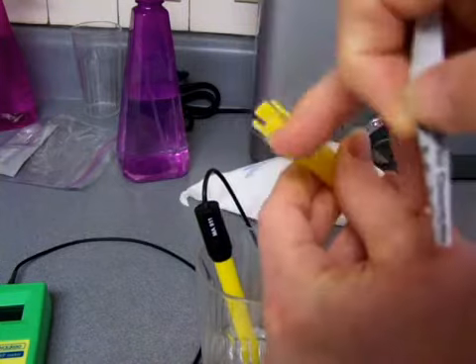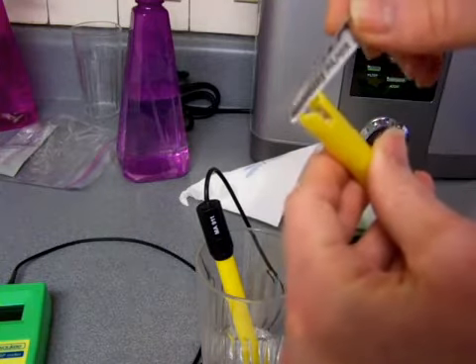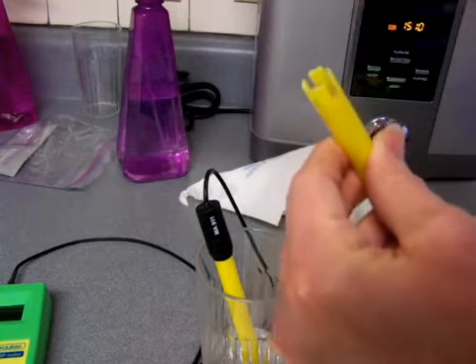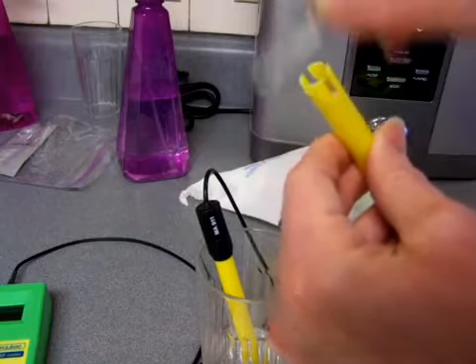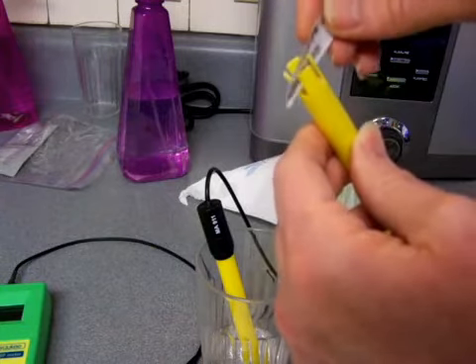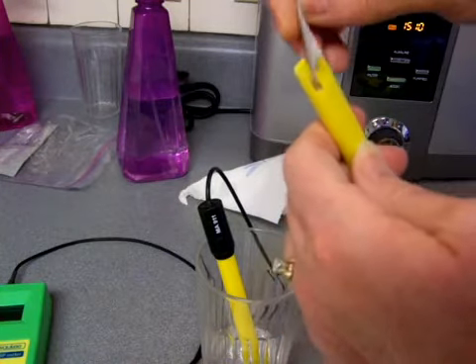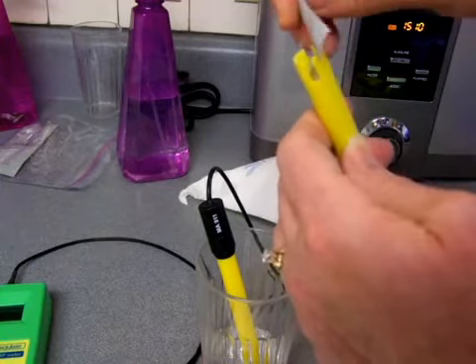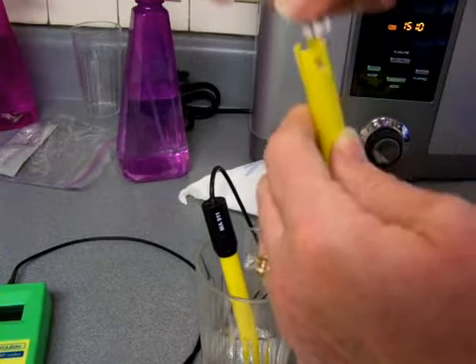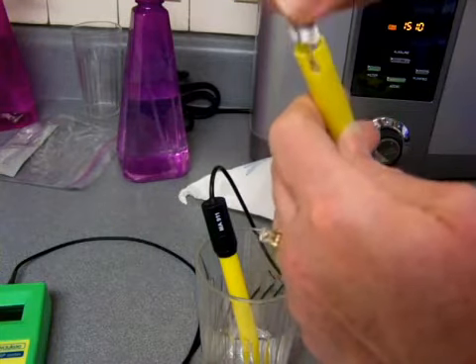And then I just go, there's little grooves here on the sides of the probe, and I just kind of go in the grooves and just do very light swishing and sanding. Very, very light, not hard. I don't want to do so roughly hard that I remove the platinum, of course. I just want to lightly polish it and get that calcium off.